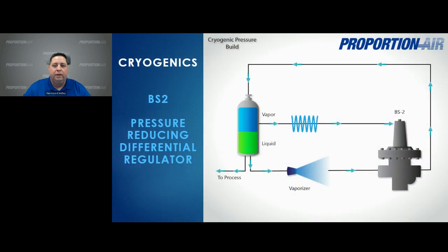An application that can also often be successful with a spring-loaded regulator is cryogenic pressure building. Here we're showing how a pressure-reducing differential regulator maintains pressure in a vapor space above liquid in cryogenic vessels, like a Dewar container. The liquid in the lower part of the vessel is vaporized before reaching the regulator's body, which is a set pressure determined by the spring position and the seat placement.